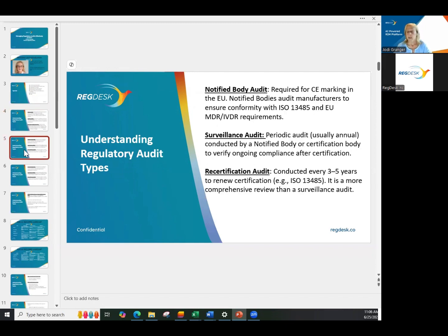In terms of the EU audits, there are different terminologies used for these audits. You typically have your initial notified body audit. This is where they're going to look at your entire quality management system and issue you your initial certifications for ISO 13485. From that, you will continue to have audits on a routine basis by your notified body. They have surveillance audits and recertification audits.